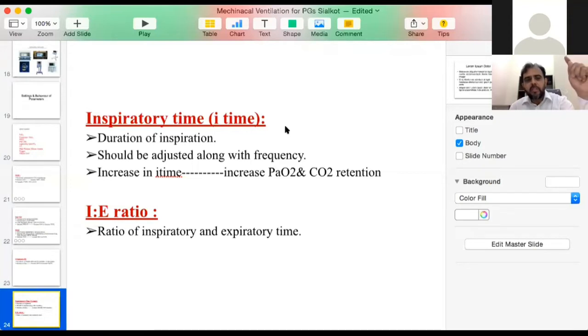If a child is breathing at a rate of 60 breaths per minute, then in each second, one breath is being delivered. If you make a dissection of that one breath, each breath has inspiration and expiration. Normally, the inspiration time is 1/3 and expiration time is 2/3. So if we divide this total 1 second into two parts, it will be 0.3 second and 0.7 second. This is the normal distribution that we see in normal breathing. But we can change it. We can increase inspiration time to 0.4 and reduce the expiration time to 0.6. So we can manage the IE ratio.